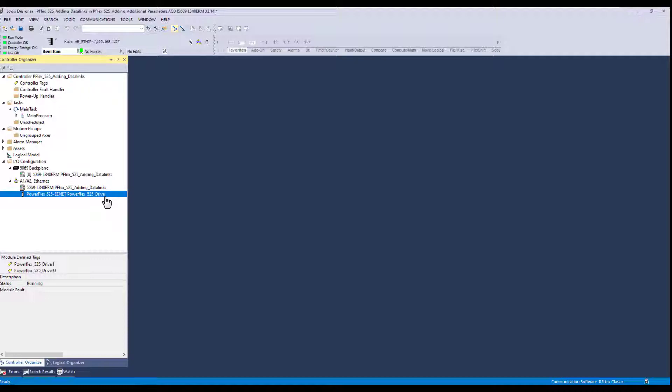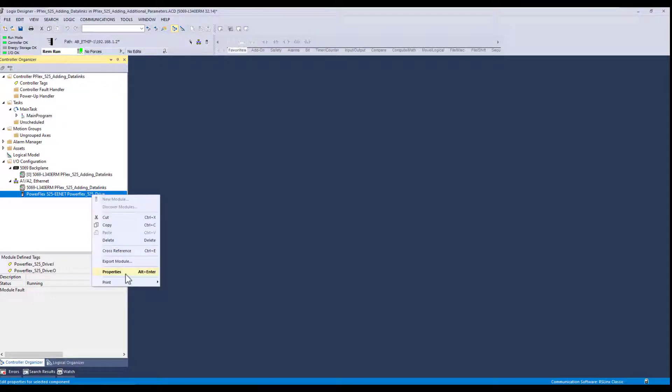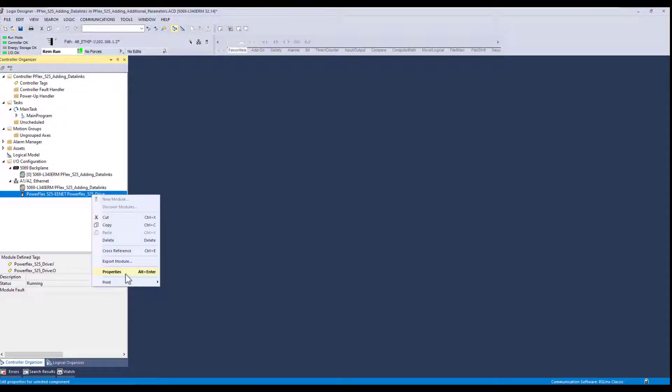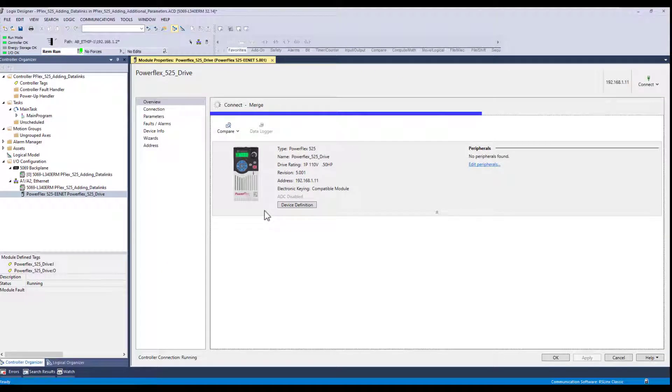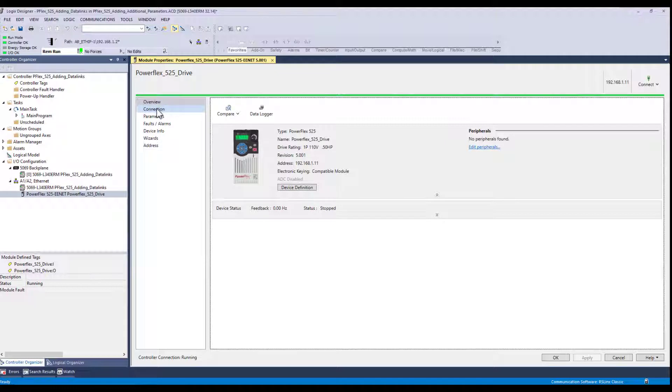So I can either double click here on the PowerFlex drive or just right click and select properties. And the first thing you need to do is disconnect the connection between the PLC and the drive communications.